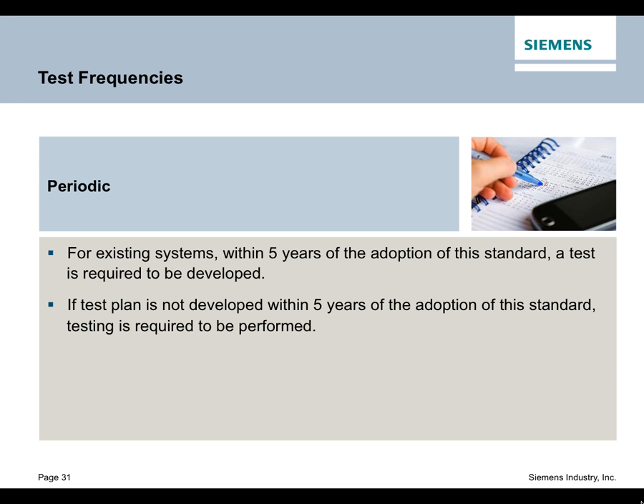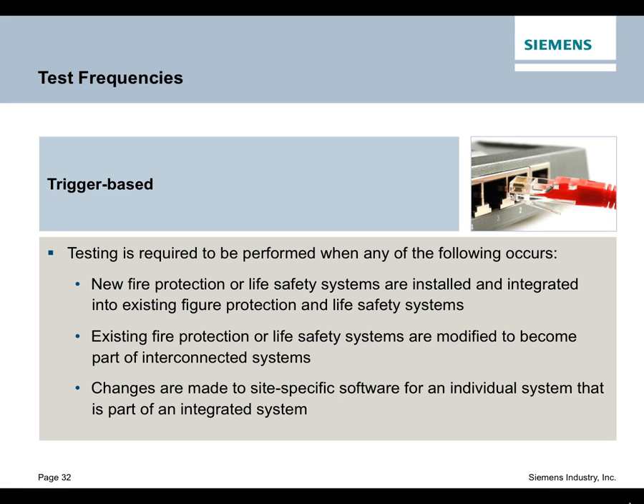And the code, NFPA 4, allows you to have discretion when you're creating your test plan to use good engineering judgment, and the advice of your authority having jurisdiction, your insurance companies, and your ownership, as to how often that should be done. This is not intended for the Subway or the McDonald's that may technically have an integrated system to have to be retested every 5 years in the integrated fashion. Those things maybe don't have to be done for every 15 years. But when you have a high-rise hospital with lots of integrated stuff going on and the probability of making sure that stuff works is at a higher risk, the recommended median is about every 5 years that the integration should be retested. It could be done at a greater frequency. It could come down to every 2 or 3 years if, once again, it's deemed to be needed at that frequency. The important thing is that this stuff does get identified and does get tested from end to end.